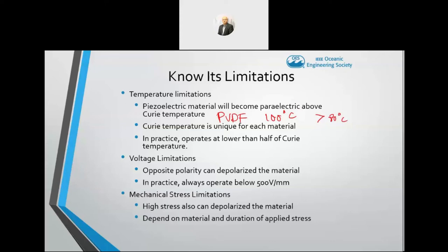So the Curie temperature is unique for each material, and in practice, operating at lower than half of the Curie temperature is the safest rule of thumb for underwater acoustic sensors. For example, if we are using PVDF as our piezoelectric material, the maximum temperature should be below 50 degrees Celsius.